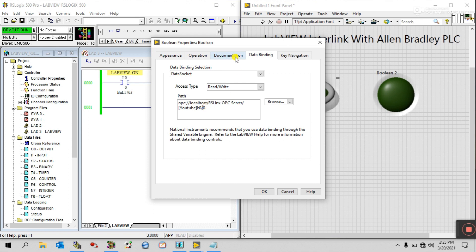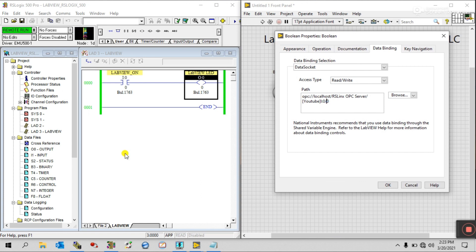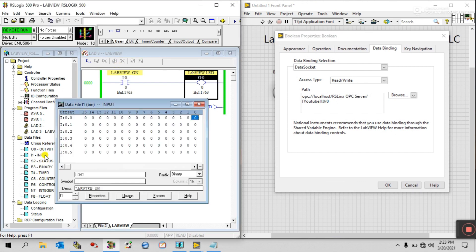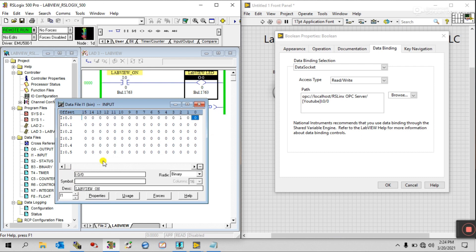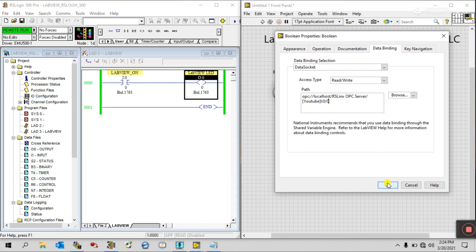We need the input. Find I1, and you can see the pins. I am choosing I:0/0. Now, 0.0 means the full word bit — 0 to 15. But I need only pin 0, so I modify it to I:0/0 (0 slash 0). That's why we choose 0/0 — it selects only pin 0. Click OK.